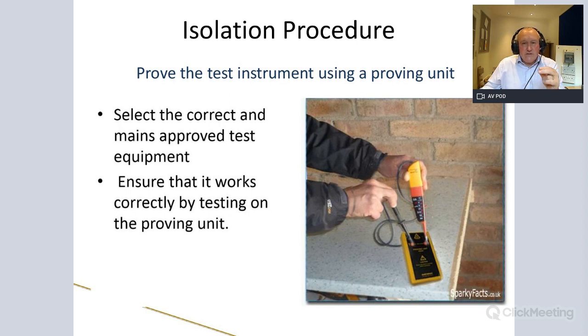We then test the voltage indicator against a known supply. That could be the actual main supply coming into the board, since that's on the other side of the breaker, but most people use a proving unit, as I mentioned.